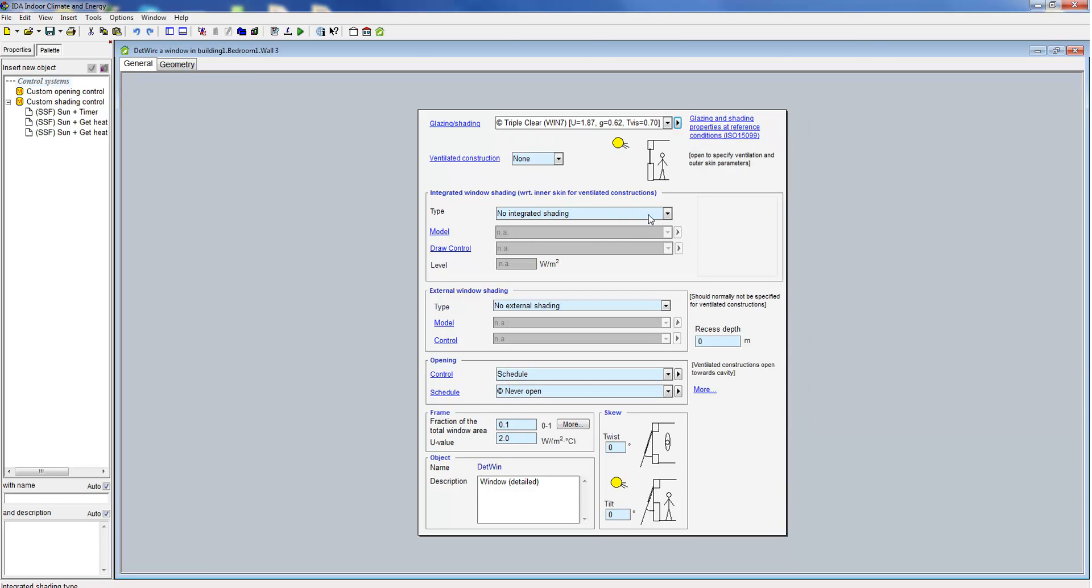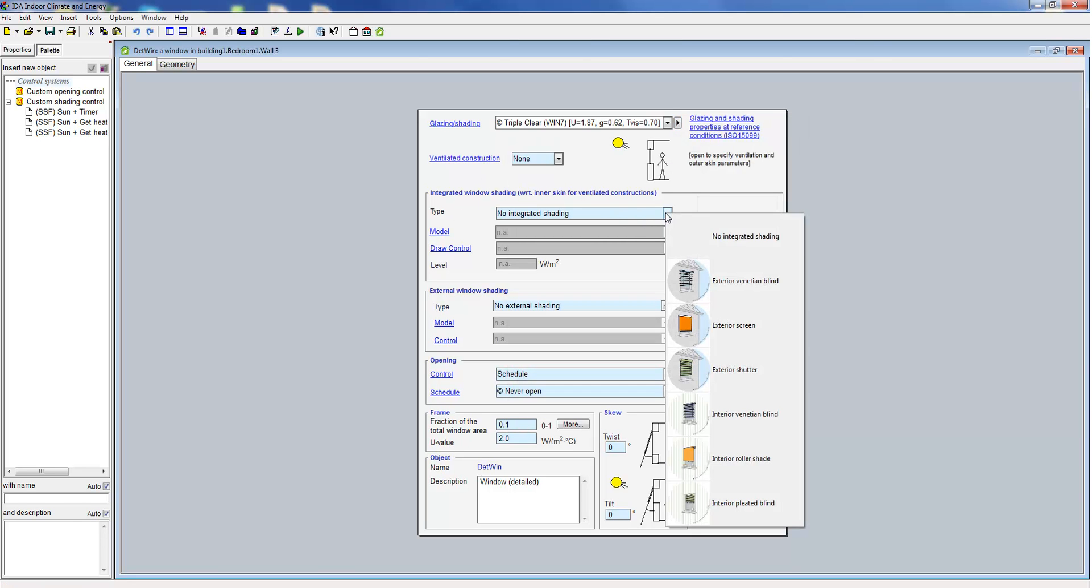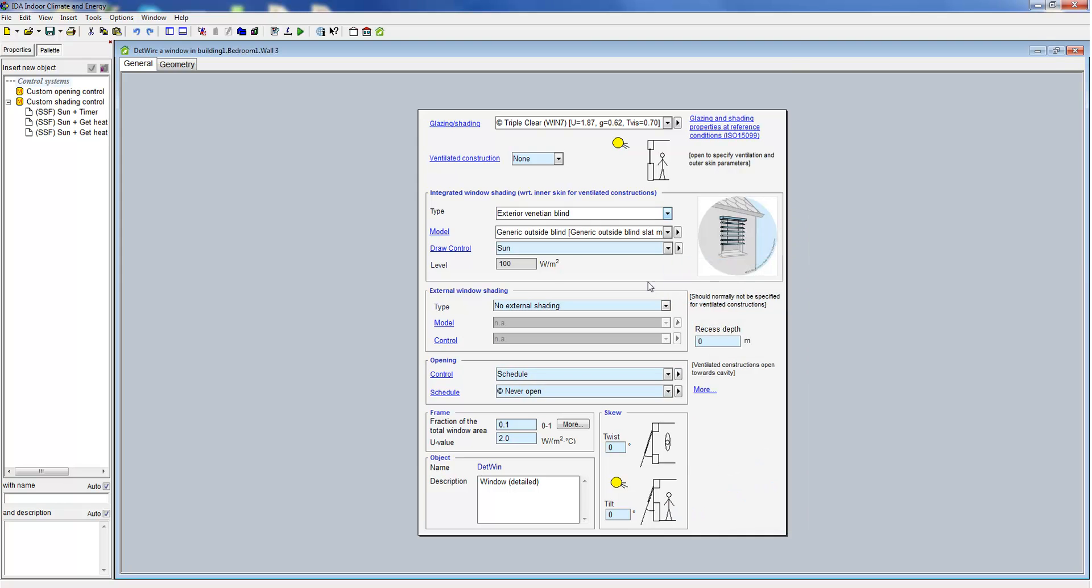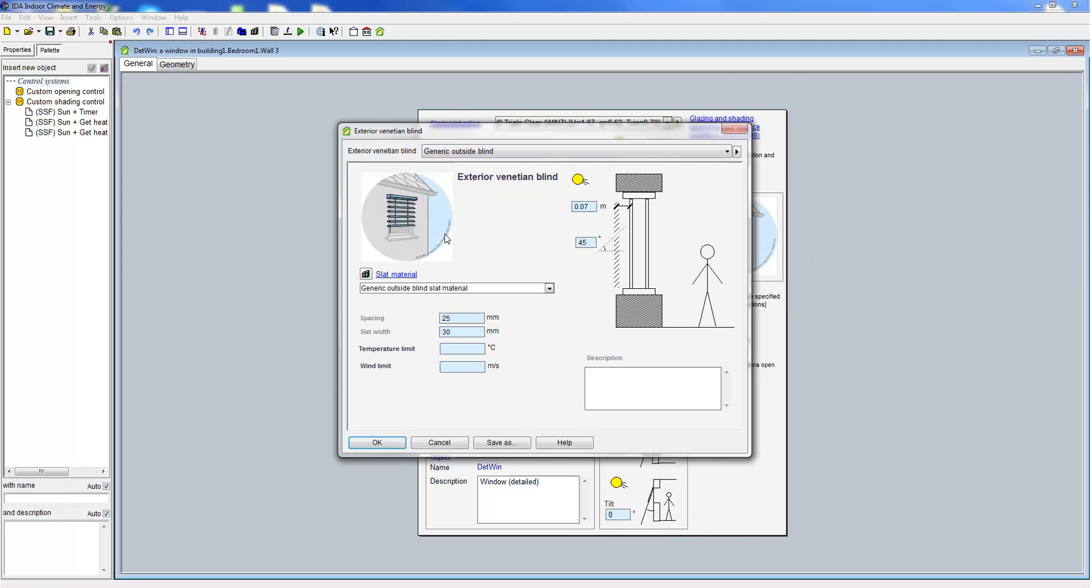For the detailed window model the user can again define an integrated window shading. However, the treatment of the shading in the model is a lot more detailed. The spacing and width of the slats is defined and also the slat angle. The latter can also get controlled and altered over time.